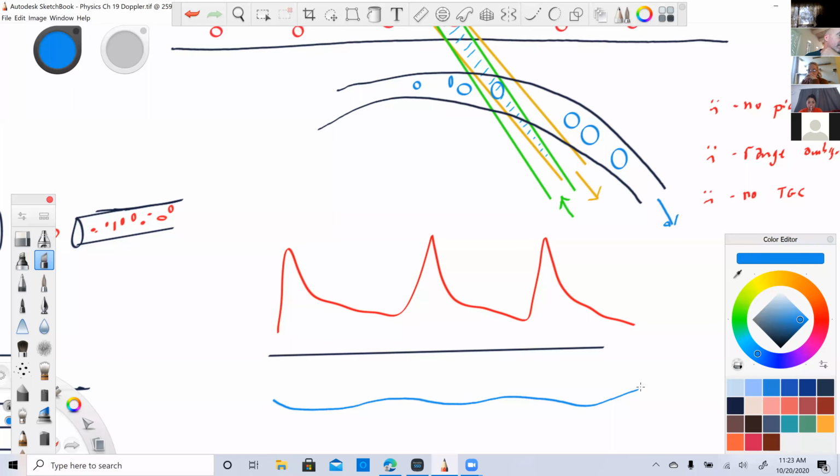Dedicated continuous wave transducers do not use backing material. This results in the following: undampened transmitted signal, which creates a narrow bandwidth, a high quality, high sensitivity. Matching layers, of course, are going to be used. And I kind of already talked about pulse wave.